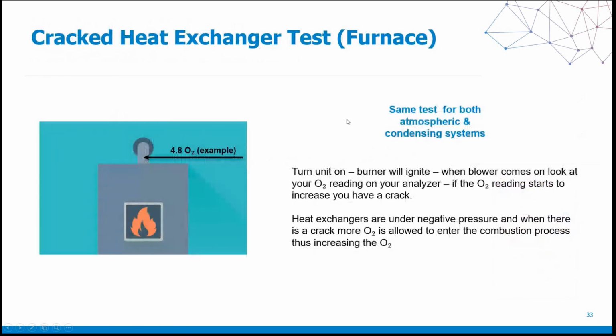Cracked heat exchanger tests. This is something that you would do on a forced air system, and it is very important. It doesn't matter the experience level of the technician, because an analyzer can help the most inexperienced tech look very intelligent and can also bolster the most experienced tech's credibility. When you're an inexperienced tech relying solely on visual inspection of a cracked heat exchanger, there's a pretty good statistical chance you might miss the crack. However, an experienced tech could miss it as well. So there is a high level of variability there. Well, a combustion analyzer negates or solves that variability quotient.